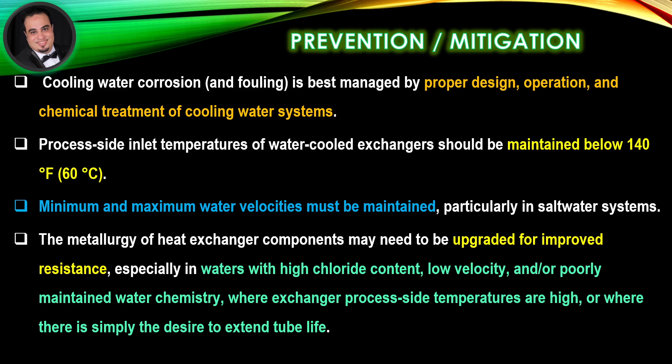Minimum and maximum water velocities must be maintained, particularly in salt water systems. The metallurgy of heat exchanger components may need to be upgraded for improved resistance, especially in waters with high chloride content, low velocity, and/or poorly maintained water chemistry, or where exchanger process side temperatures are high, or where there is simply the desire to extend tube life.